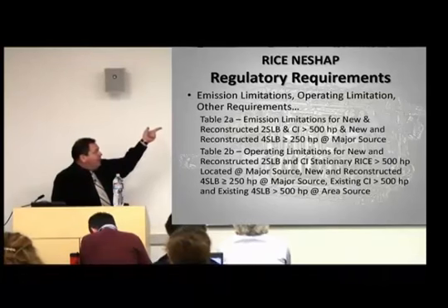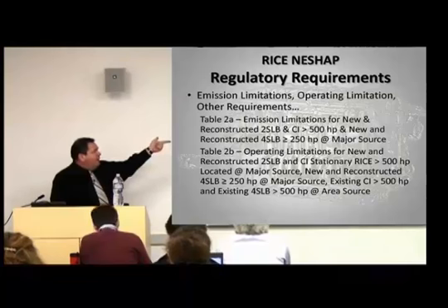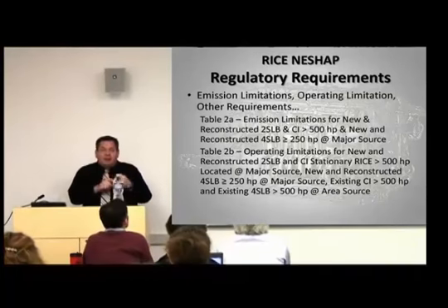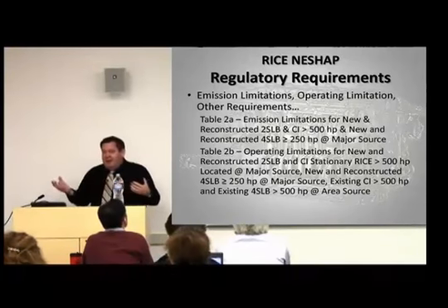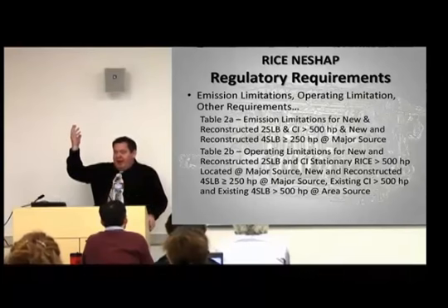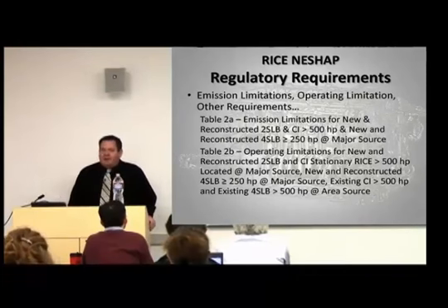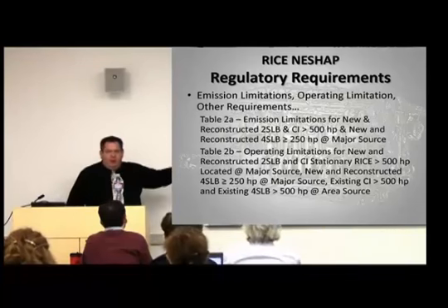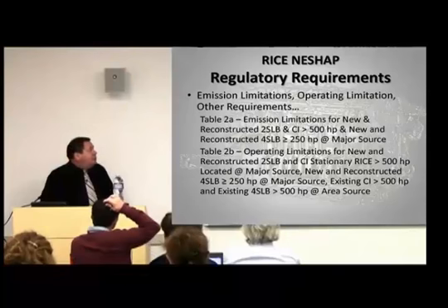Here's table 2A for emission limitations, table 2B for operating limitations on lean burn spark ignited engines and compression ignited engines, because compression ignited engines are also lean burn engines. Well, lean burn engines have lots of surplus oxygen coming out of their stack. Therefore, they would not be candidates for non-selective catalyst. They would be candidates for oxidizing catalysts. So their requirements are limited in these two tables.